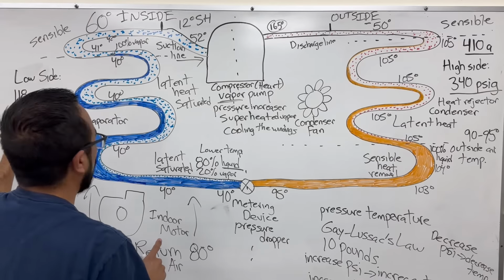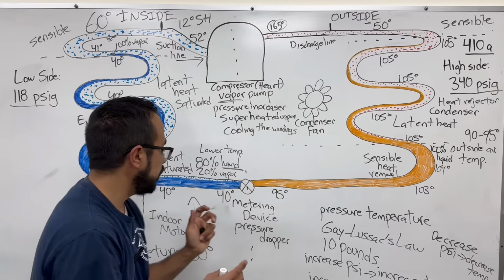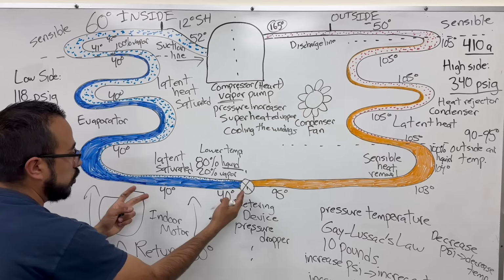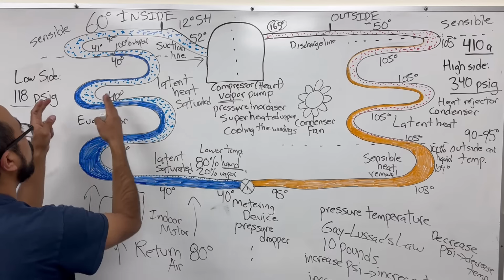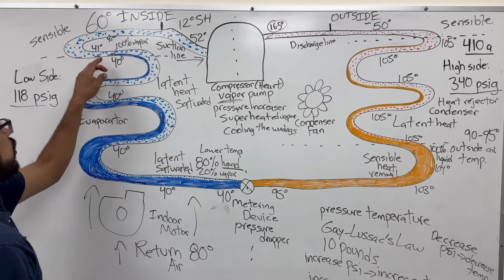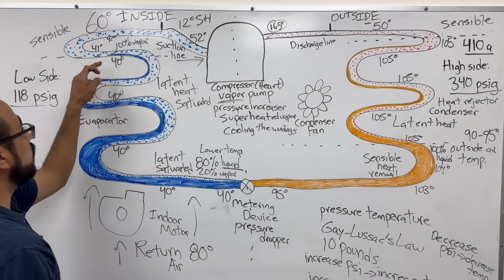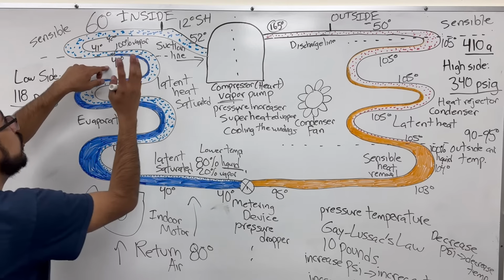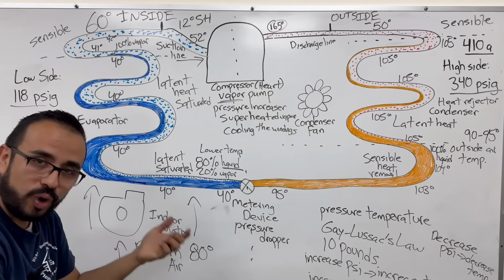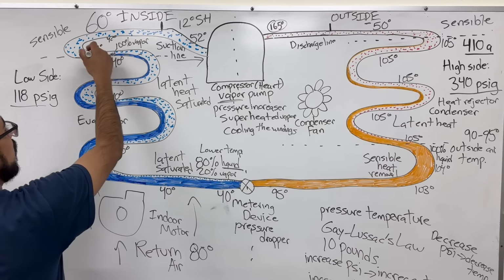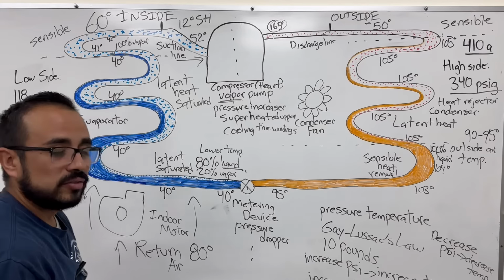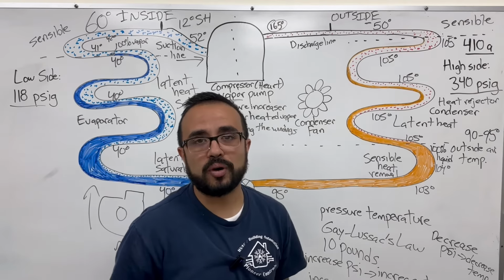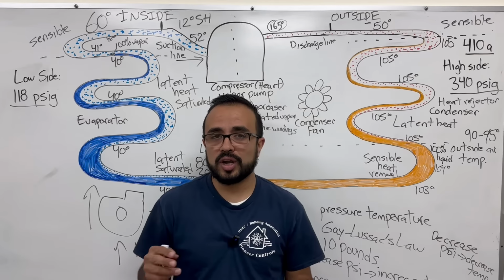We connect our hose to the low side of the system. And so we got saturated, 40, 40, 40, boom, until that one last molecule of liquid is gone. We're boiling off that liquid because the return air has heat going through that cold coil, coming out cold. And now we get our superheated vapor. So you see why it's so important to have heat transfer.